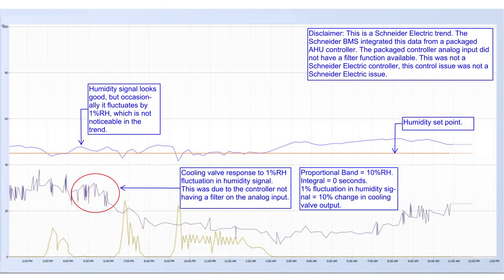Now, another thing that I've seen is the BMS controller on the analog input, there should be a filter in there. So sometimes the process variable, whether temperature, humidity, pressure, CO2, CO, whatever it is, is fluctuating a little bit. And the PID loop sees that little fluctuation and it moves the output 51, 50, 51, 52, 51, 50, 49, a tiny little bit, you wouldn't even notice it. I've seen this loads of times. I said to the BMS guy, hey, look, you need to put a filter on the analog input. Let's have a look at it.